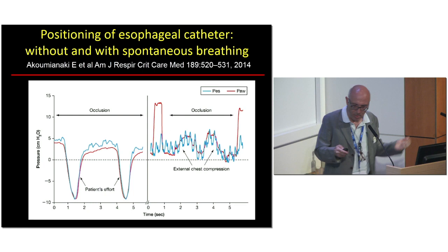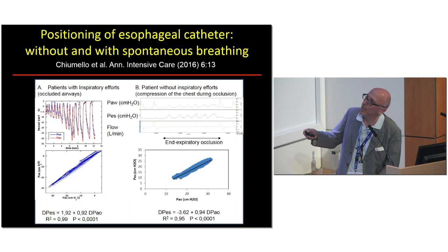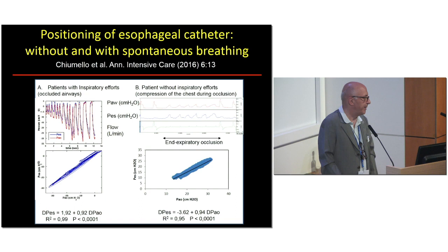You see here, this is the changes in esophageal pressure and airway pressure in spontaneous breathing at the occlusion, or during inspiratory effort with compression of the chest during occlusion. This is the curve you would expect between changes in esophageal pressure and airway pressure, which should be more or less the same within 10%. This is the occlusion method. Is it clear?